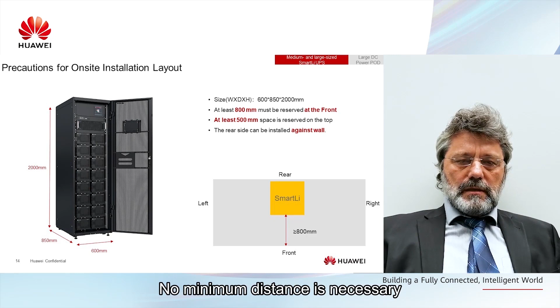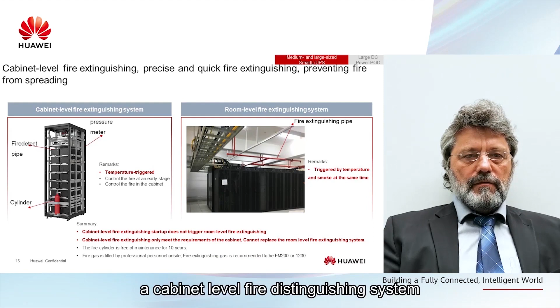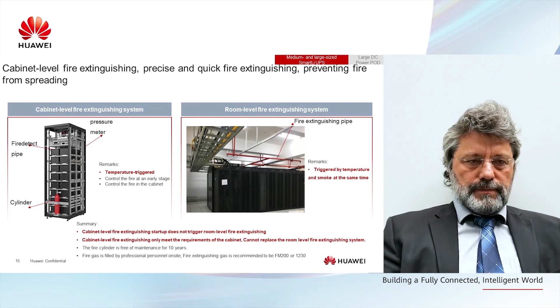Cabinet level fire extinguisher. Using lithium batteries is a concern to many users. Despite our safe LFP technology and our comprehensive BMS, we added a cabinet level fire extinguishing system. It operates on a fire detection pipe and it is temperature triggered. It has an on-site filled gas cylinder which is pressure monitored to ensure always availability of the firefighting system. The system works independent from the room level fire extinguishing system and will not trigger it.